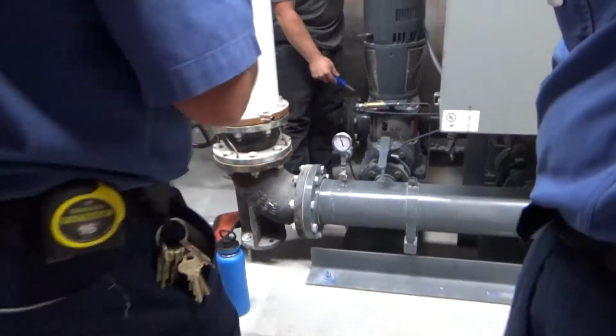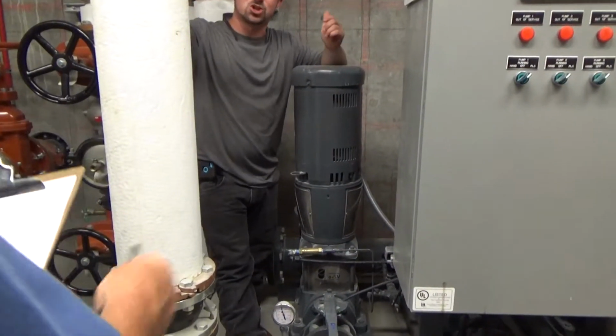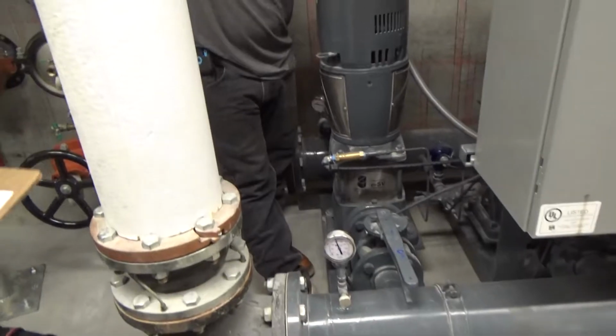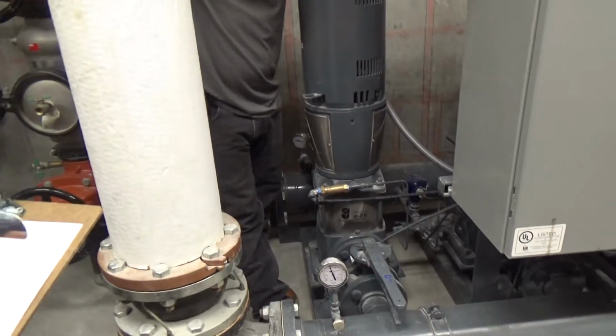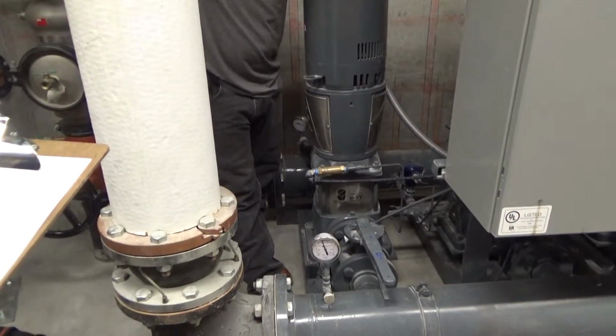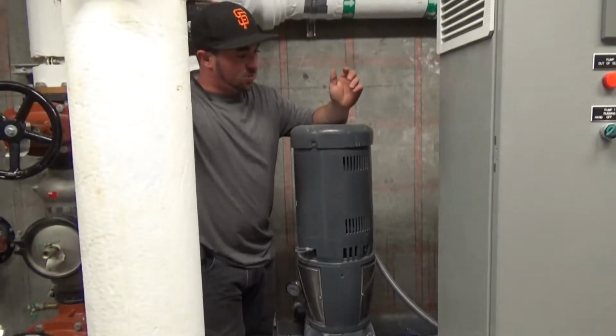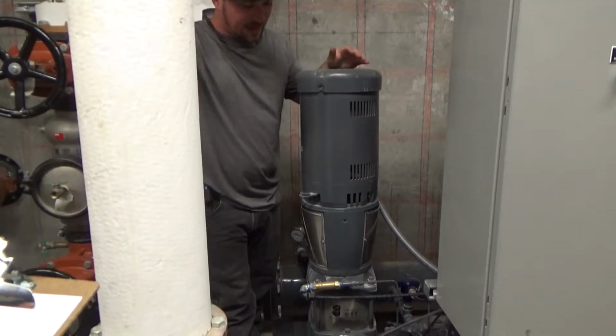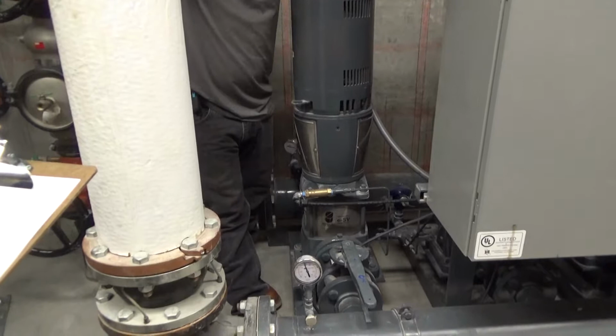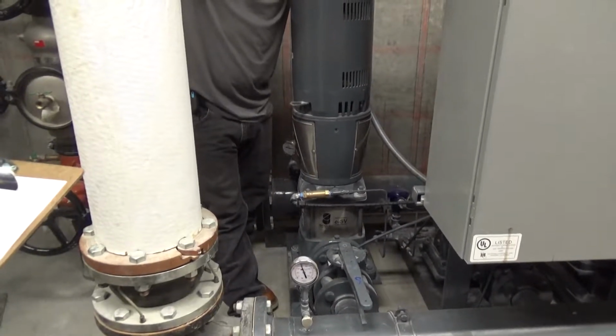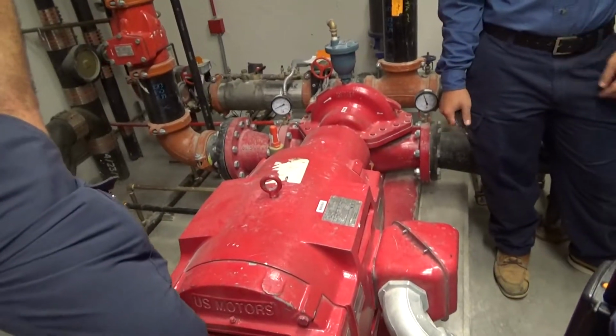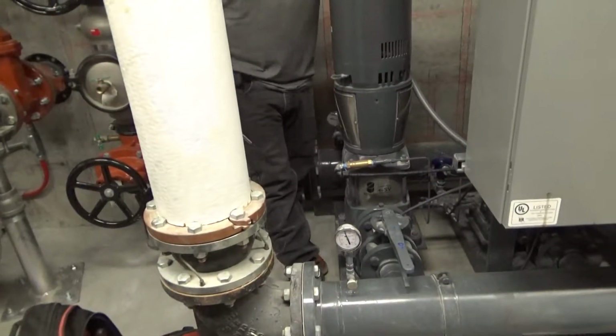Can you get somebody at the factory out here to show us how? Pumps, they have numerous impellers inside of there. The whole point of having numerous impellers is it's more efficient. These are high head pumps, which means they can put off a lot of pressure and a lot of flow. These are great pumps. What's good about them is that the motor is vertical like that. It's really good on getting the heat off of the motor, so the motors tend to last a lot longer than pumps that are mounted horizontally like that one. And they're really, really efficient.